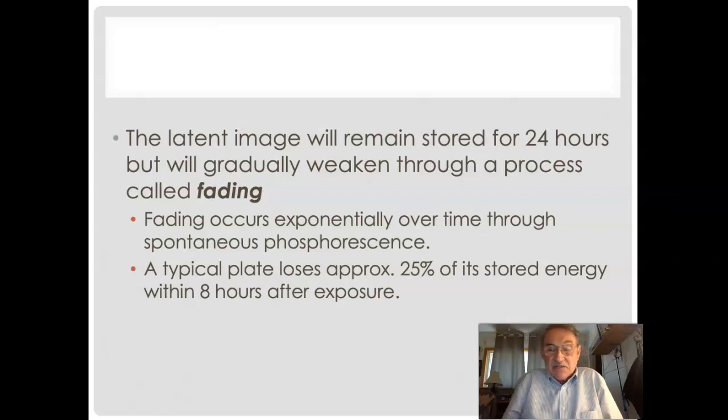Okay, so let's look at an example here. I'm going to Babyland to take a chest X-ray on a newborn. Okay, and perhaps that newborn is premature, and so only weighs 1 or 2 pounds. So I'm going to use a very, very small technique, perhaps only 0.6 mass. If that image plate remains unprocessed for 8 hours, my 0.6 mass, well, it would be like I took that X-ray image at 0.45 mass.